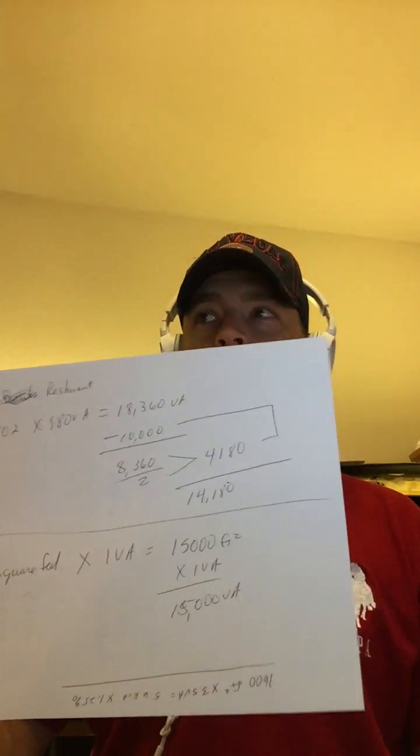Okay, so then my 15,000, I'm going to go ahead and take away the 10,000. No, you can't derate it. You can't derate it. Okay, then I'm confused then. So the second calculation is 15,000 times the 1 VA. Look at it this way. In a bank or an office building, you have to have at least a square foot expressed in volt amps. You can't have a number any less than that, no matter what. So that's a non-deratable number.